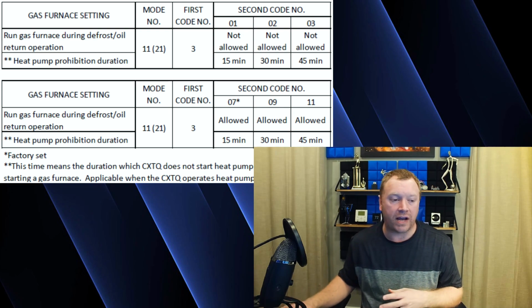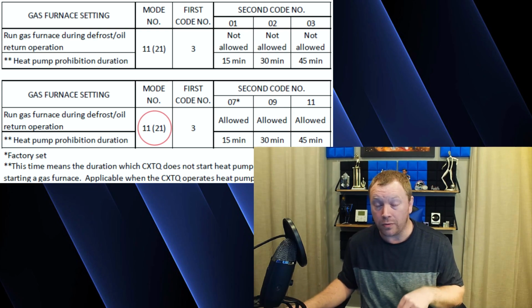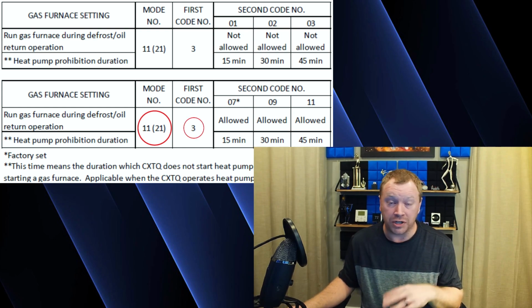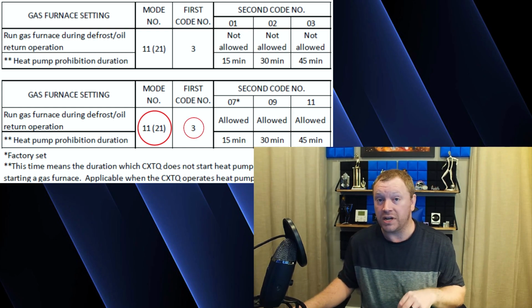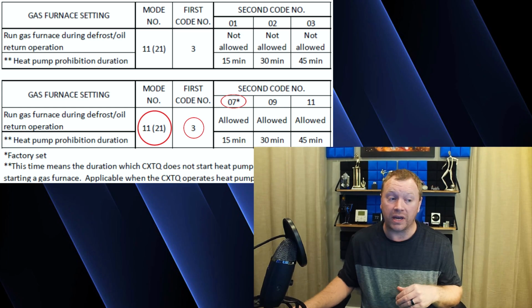Now, when you have the gas furnace, mode 21 setting 3, your default option, at least as of right now, is 3-07, which means go ahead and run the gas furnace during defrost.